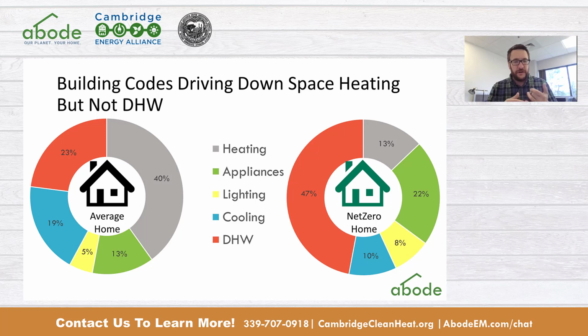But one of the loads inside of the home isn't going to be moving, and that's traditionally domestic hot water. So right now a home may need, say 60 million BTUs over the course of the year for its heating load. After it's headed in that net zero direction, that may be 20 million BTUs per year. But the domestic hot water load today is going to be 40 million BTUs. And when that home is net zero, unless there's fewer occupants in the home, it's still going to be 40 million BTUs. So at some point along this journey between today and 2050, in every single home that we're needing to weatherize and improve, the domestic hot water load is going to end up being the highest load in the house.